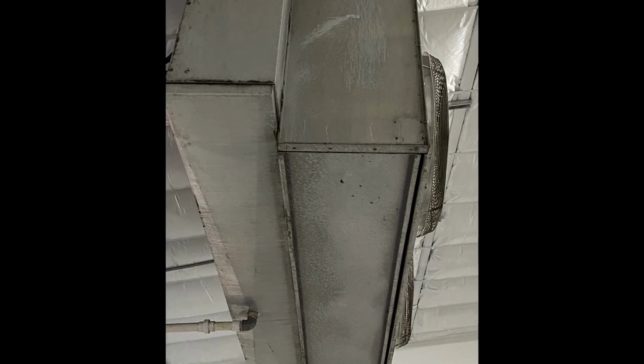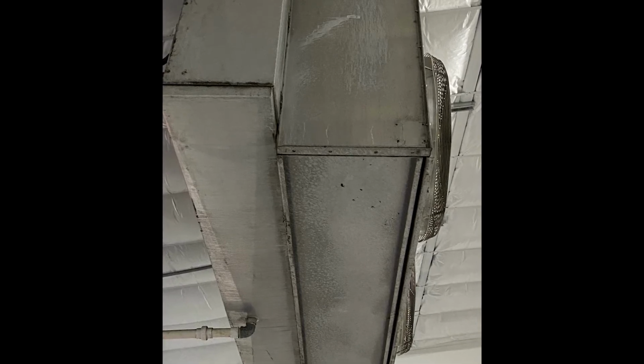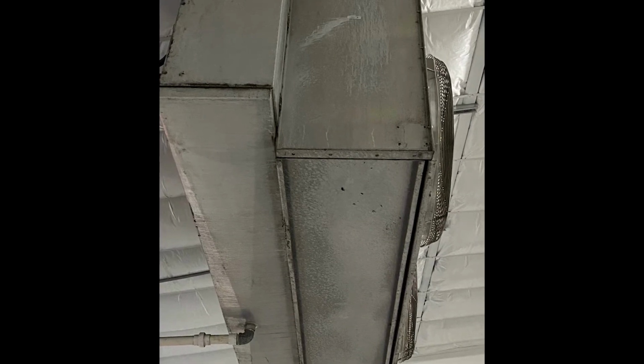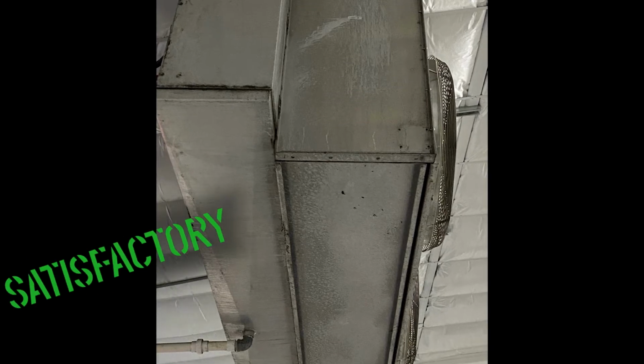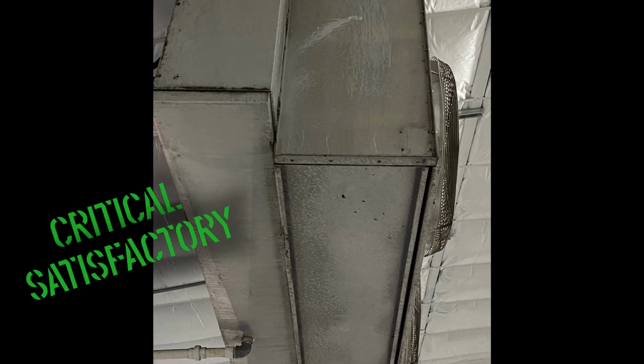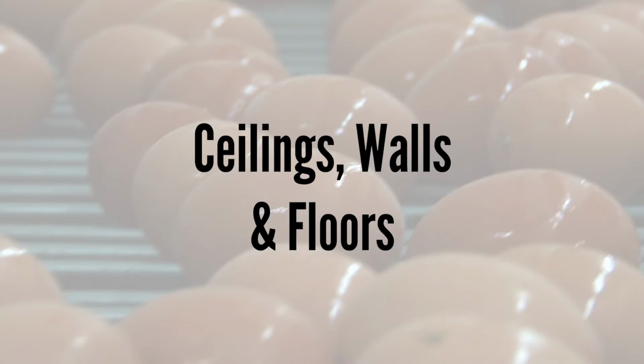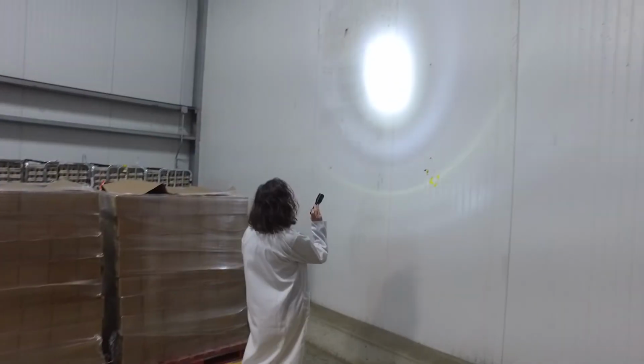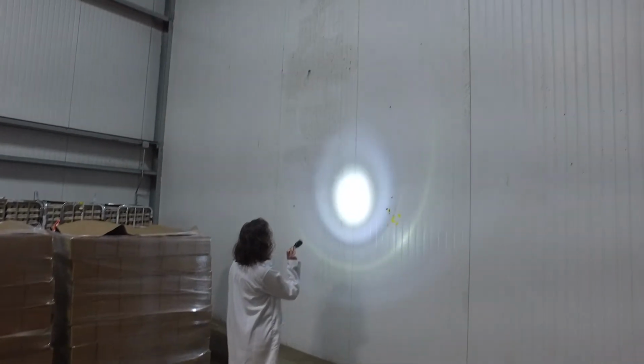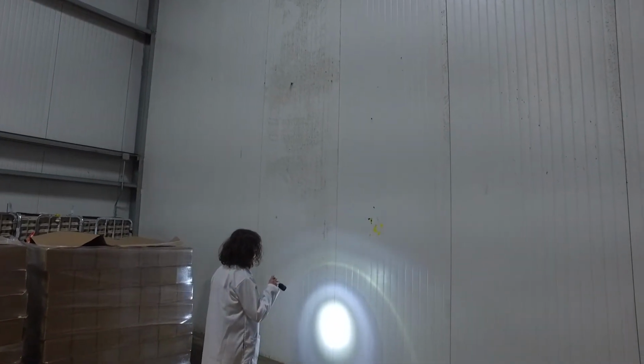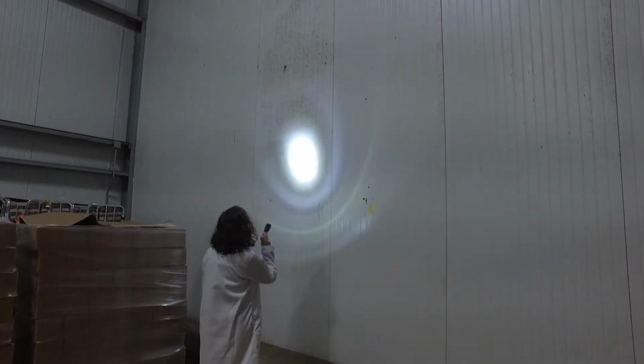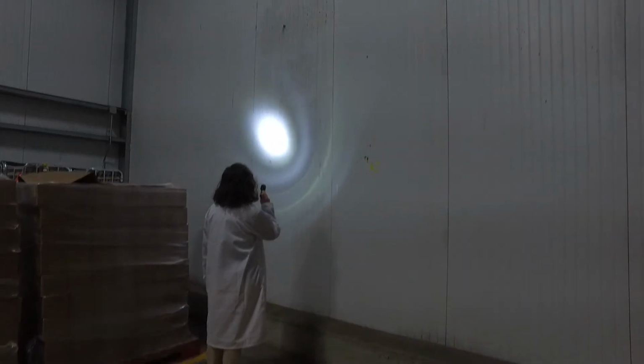The exterior panels show signs of discoloration, but show no signs of dust or condensation. This is a satisfactory finding in a critical area. Regular cleaning is necessary to prevent the buildup of dust and corresponding mold and mildew growth.